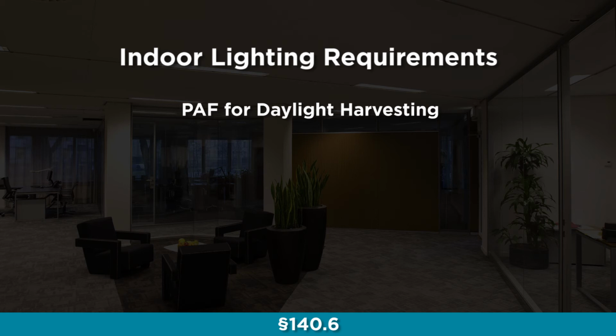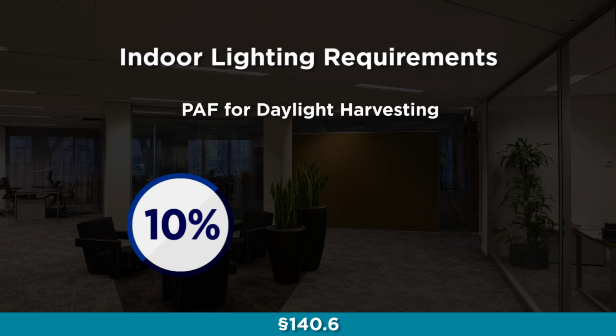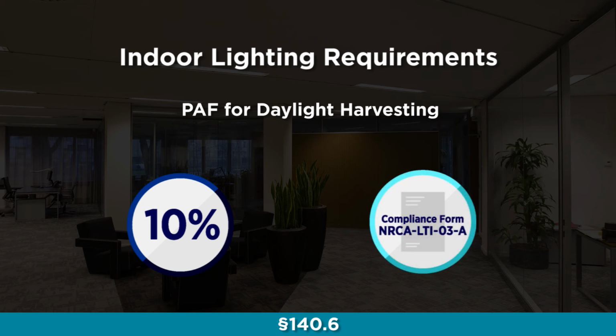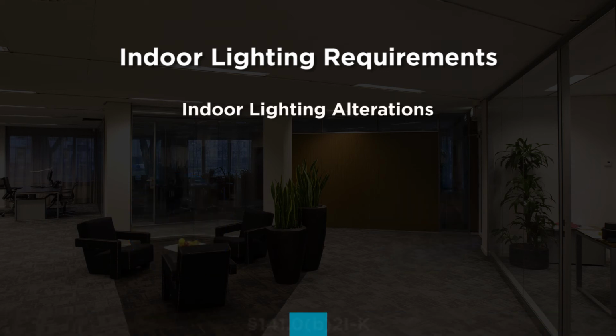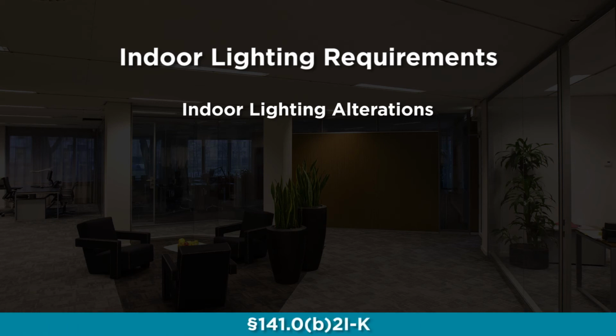The second new PAF addresses daylight harvesting control systems that fully extinguish all the lighting when sufficient daylight is available. Projects may gain a 10% credit for this strategy when applied to luminaires in a skylit or primary sidelit daylit zone. Acceptance test results for daylight dimming plus off controls are documented on the existing automatic daylighting controls compliance form, NRCA-LTI-03-A. Requirements for indoor lighting alterations have been simplified, reorganized, and renamed.